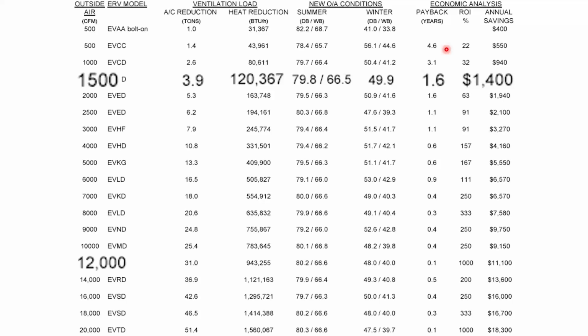One more example on here, 12,000 CFM of outside air, which is a lot, I know. That reduces my cooling system by 31 tons. So if I was looking for a 30, that wouldn't work. I was going to say a 30-ton rooftop. A 60-ton rooftop, now I'm in the market for a 30-ton rooftop, right? Almost 1 million BTUs less heat I need. And the payback is really good on this one, 0.1 years. That's like a month, right? I picked that one because it was the best payback.